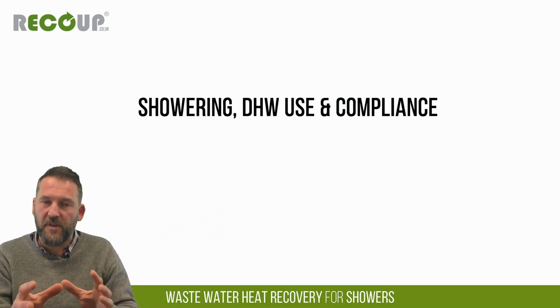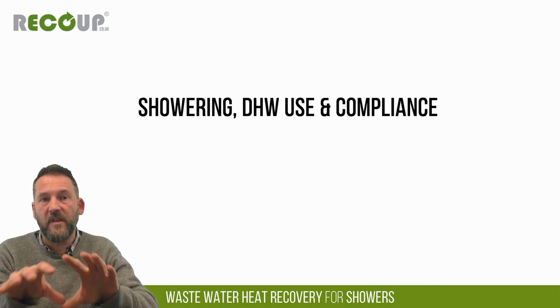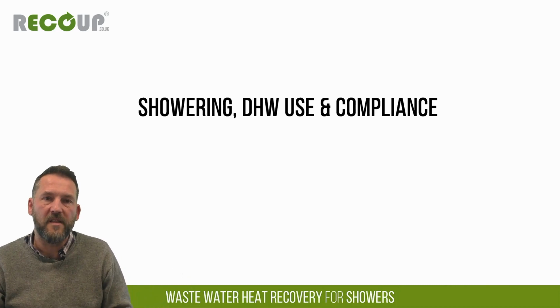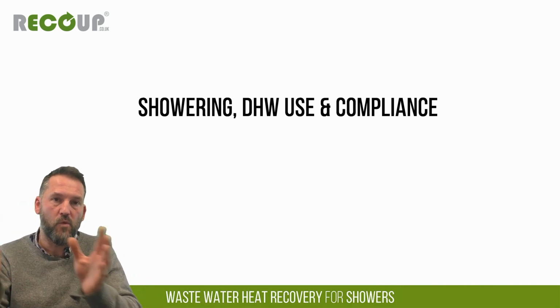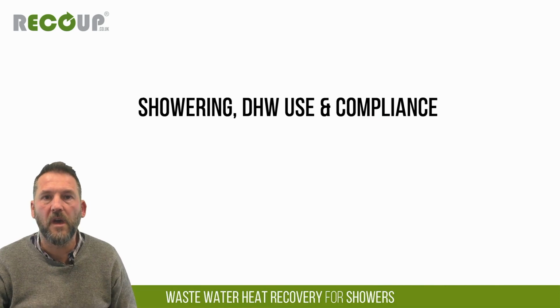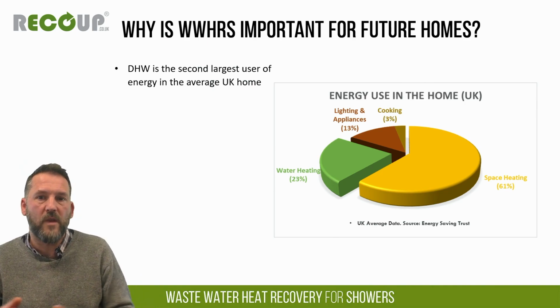So SAP doesn't attribute any energy savings to the bath. It's only to the shower, and that's the same with all other hot water outlets. It's because our heat source is that warm shower waste going down the drain. It's only used in that cycle of when there's warm waste going down and cold water main coming in. Hopefully that answers okay.